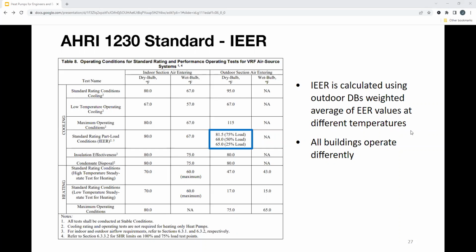But every building operates differently, right? Between the controls and the different types of equipment that's installed, whether it be heat pumps or third-party equipment, everything operates a little differently. And if you are looking for a more accurate representation of what that heat pump is going to be doing in the space, some of the best methods of approaching that are doing energy modeling, or actually installing extra equipment to do energy monitoring as well, to operate your system as efficiently as possible.